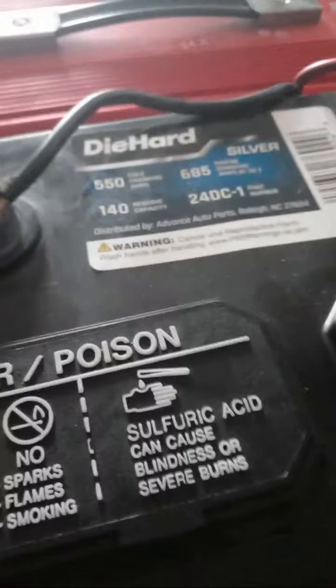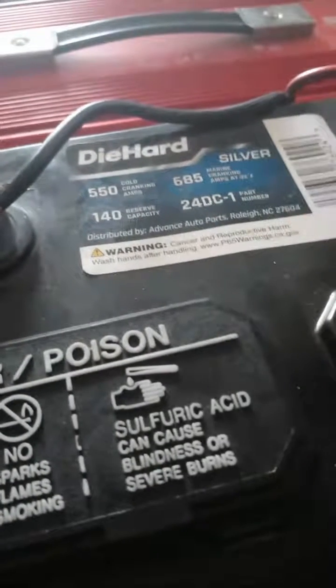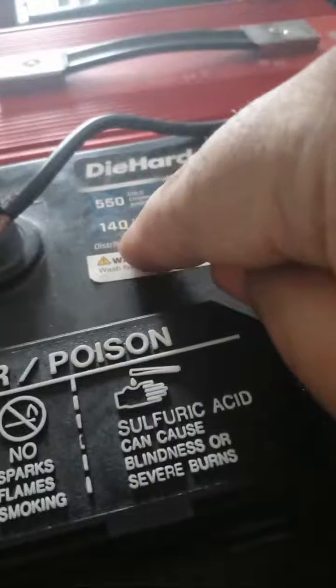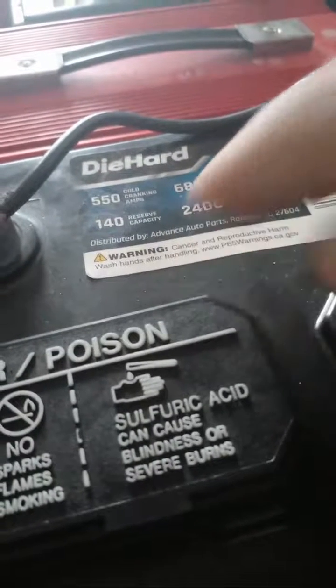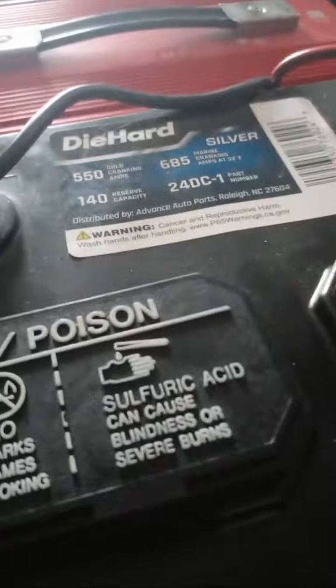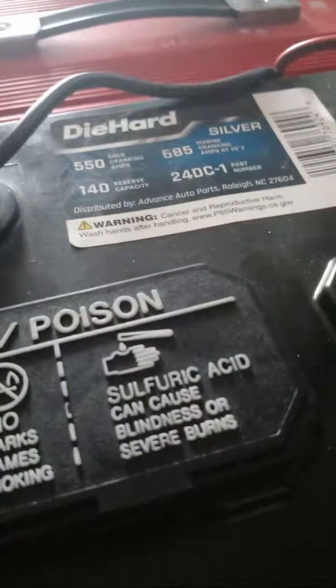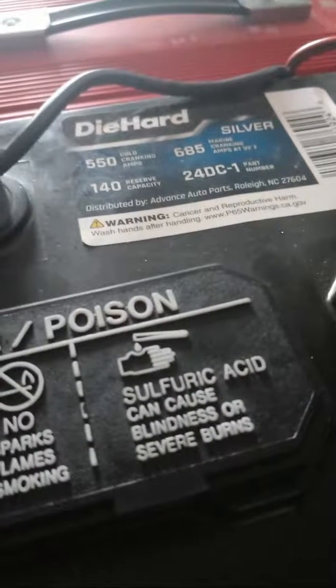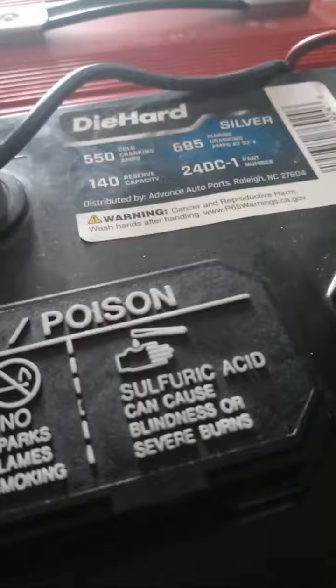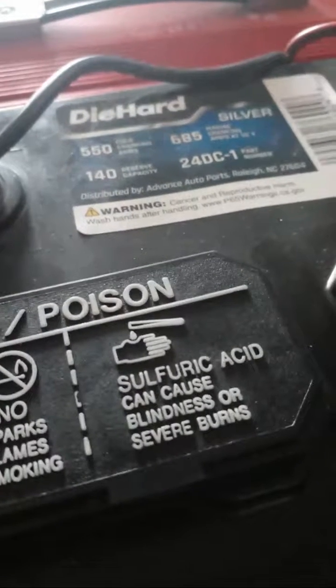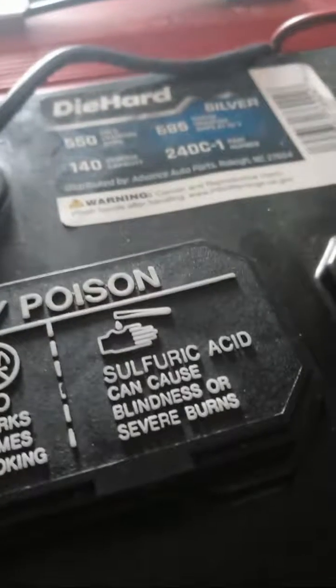The formula that actually worked for me and was more precise is this: take 140, multiply that times 60, then multiply that times 25, and divide by 3,600. So you multiply 140 times 60 minutes, which is an hour, multiply that times 25, which is the load, then divide by 3,600, and it gives you about 58 amp hours. In my experience living off grid with this system, I can attest that this last formula is the most accurate.